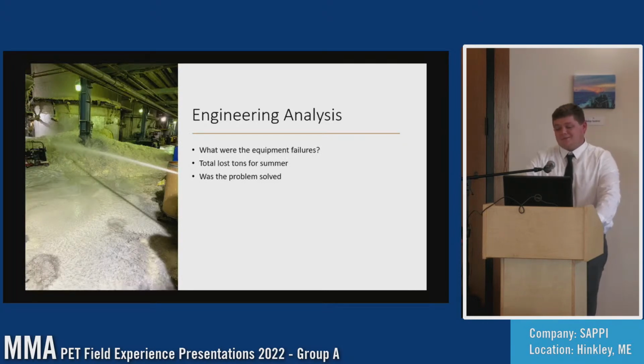The equipment failures we had: our traversing bin feeds both hog fuel boilers, and for whatever reason, by design, the two screws come together and get hung up on each other every once in a while. When I was there this summer, that happened 3 times, causing 3 boiler trips, each a 24-hour job to unstick the traversing screws and get the boilers back up and running on bio.